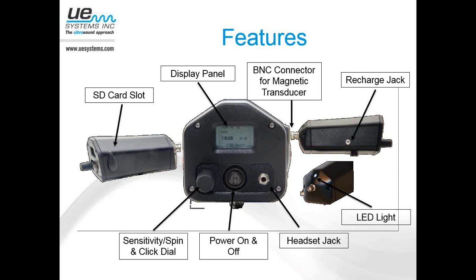So not only can we turn it left and right to adjust the sensitivity, but if we press and release, we can then navigate around the screen and we can do different things. So it's a dual purpose there. The power on and off button, you'll see that also serves a dual purpose now. Not only will it power it on and turn it off, but that's also how we input the number of strokes of grease that we have added as we're out collecting the data.